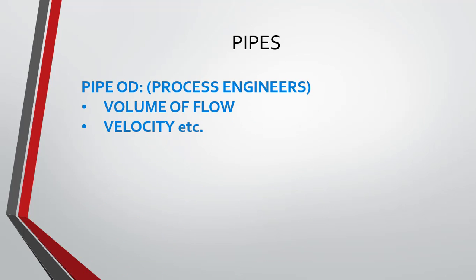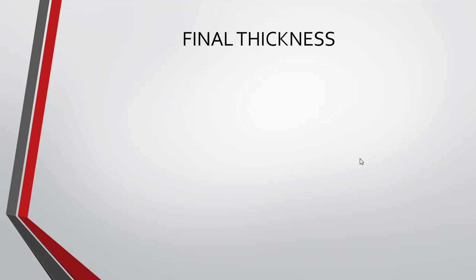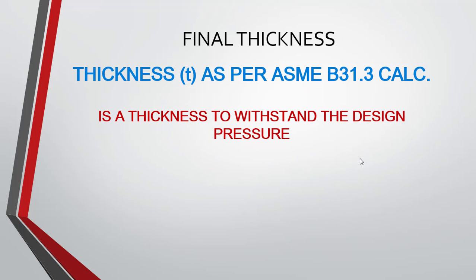The piping OD, which is the outside diameter of the pipes, is basically calculated by process engineers based on certain factors such as volume of flow and velocity, among other parameters. However, pipe thickness has to be calculated by piping design engineers based on the thickness calculation available in ASME B31.3. ASME B31.3 clearly provides the pipe thickness formula. But is this the final thickness? No — the thickness calculated from ASME B31.3 is the minimum thickness required to withstand the design pressure.